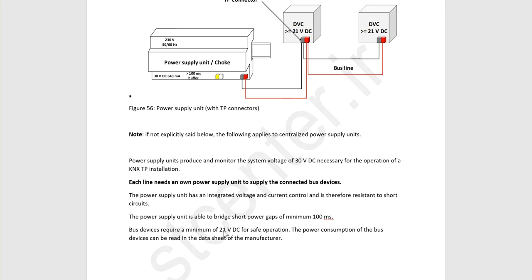But remember that after the installation, you should always check the devices that are put far from the power supply unit and make sure they have at least 21 volt DC, okay? Because if the voltage is below 18 volt DC, then the connection will be stopped automatically by the transceiver in a bus coupling unit. Okay, the power supply unit provides 30 volt DC for the devices. The power supply unit has an integrated voltage and current control and is therefore resistant to a short circuit. Okay, so there is a control.